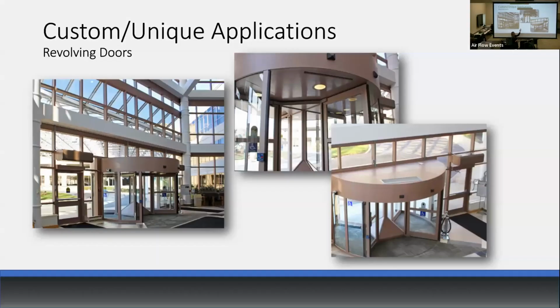Revolving doors. This is a top air intake, air curtains electrically heated. This is a medical facility or hospital. That air was getting trapped in the pockets, going into the lobby area, freezing it out. So it wasn't stopping it, it was just kind of heating it, acting as a space heater.